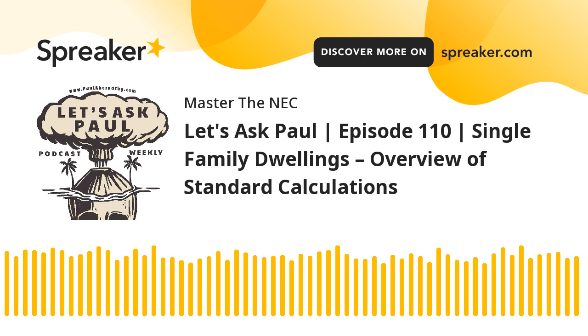So you take the first 3,000 of whatever this adds up to, from, again, the general lighting and receptacle loads at 3 VA per square foot, plus the minimum of 2 small appliance, and then the minimum of 1 laundry. You add that all up. You take 3,000 away from that and put it to the side, because that's 100%. Whatever is remaining above that, you multiply by 35%. And that value gets added back to the first 3,000, which was at 100%. Because that's what it is. 100% of 3,000 is 3,000, right? And then that's the value that you're going to use, and that completes the first step, okay? That's the first cumulative step that you have, okay?